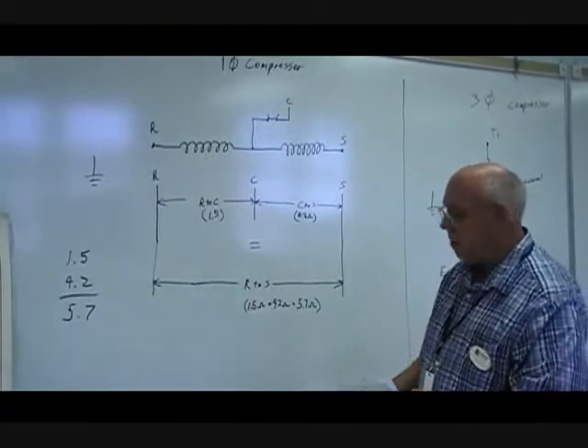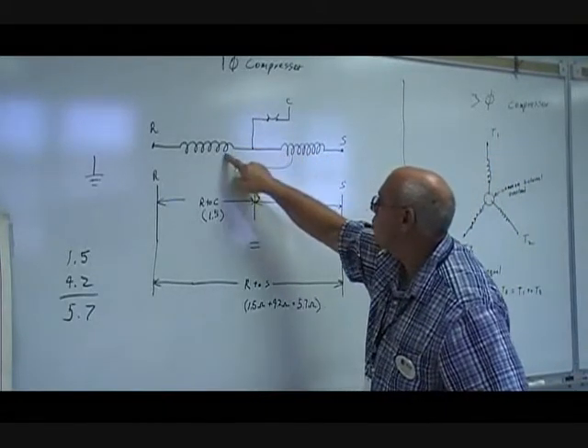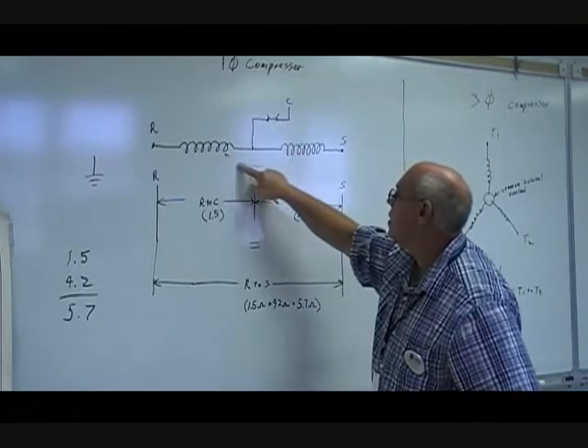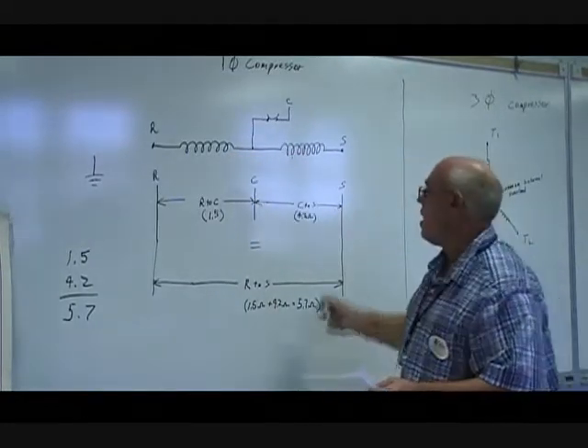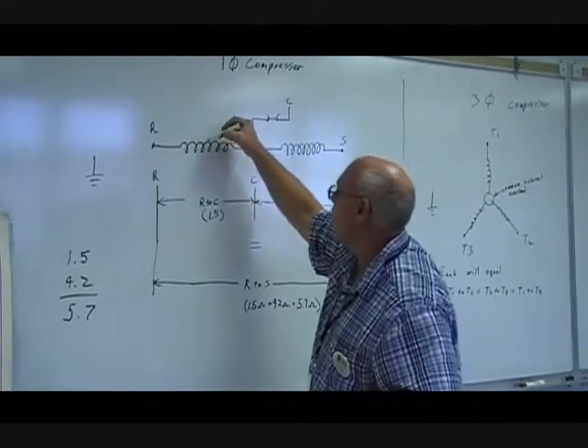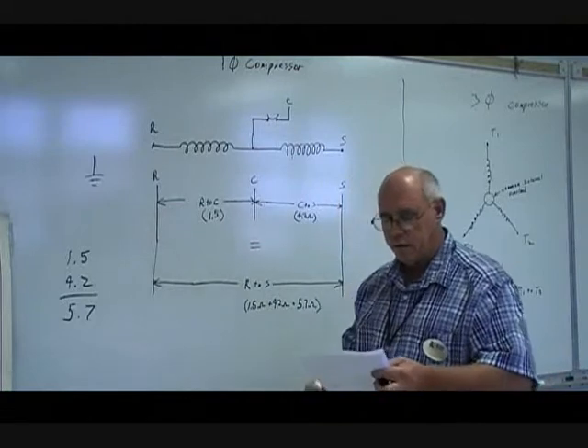Another would be a start to run internal short. In that case, they're not going to add up correctly. Another would be where we would have maybe a start winding shorted to ground. In that case, we would wind up with resistance to ground.